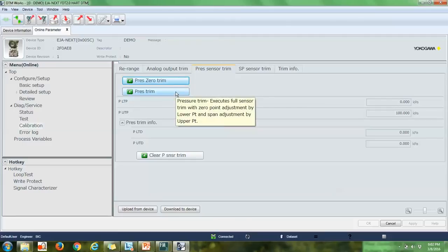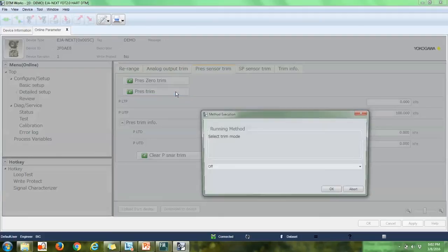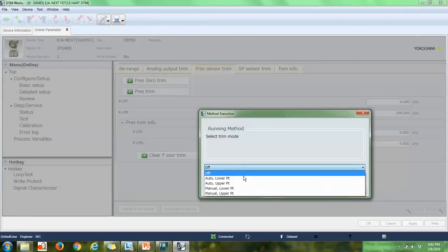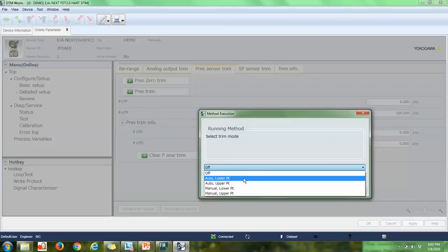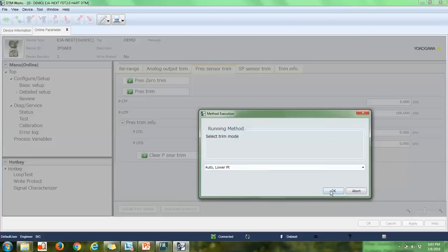So if I go here to pressure trim, I'm going to do auto lower point, so that's your zero trim, or your lower scale trim. We're going to do auto. Manual allows you to adjust it manually. Let's say you're on the high end, you're reading 100 kilopascals, and you notice on your calibrator that the calibrator is measuring 102 kilopascals. For manual, you'd have to do the math, 2 kilopascals, and make that adjustment that way. Auto allows you to just take whatever you're reading on the calibrator and trim to that. So if it's reading 102, you put in 102 on this trim for auto, and it makes the adjustment. So we're going to do auto lower point. Okay.